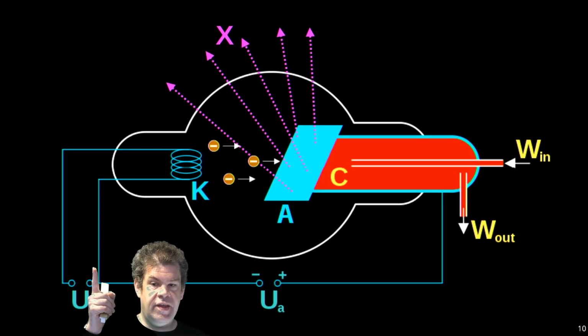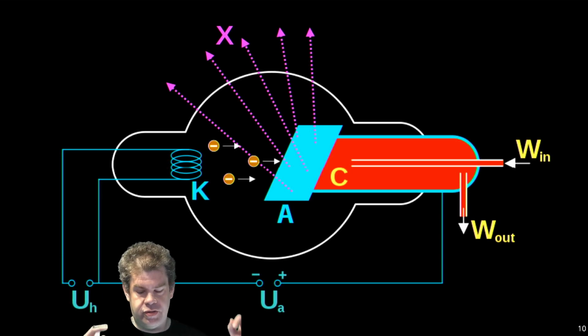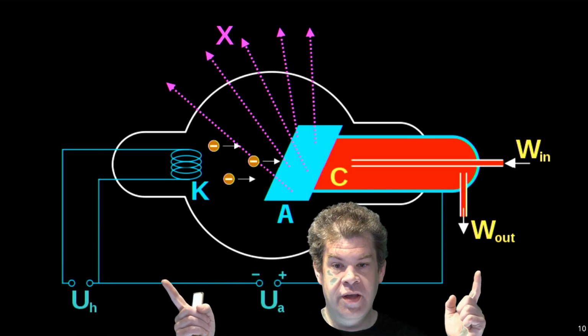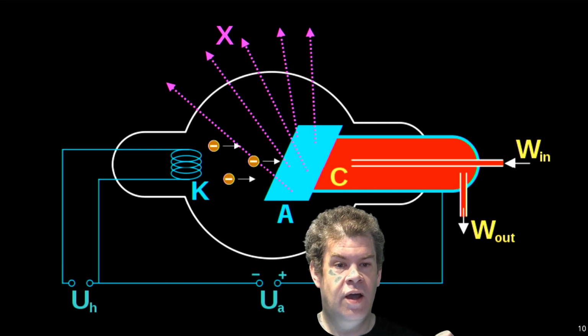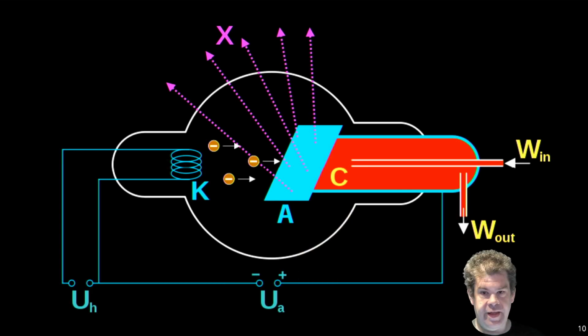Now, at the same wire, you apply an extremely high voltage, from here to here. But there's no connection. So it's just a high voltage, but at least at this point, no current, except for the capacitive load at the beginning. So we use a very high DC voltage.